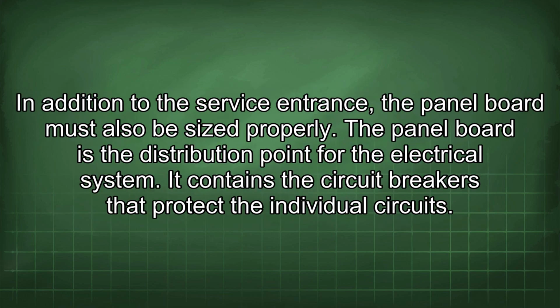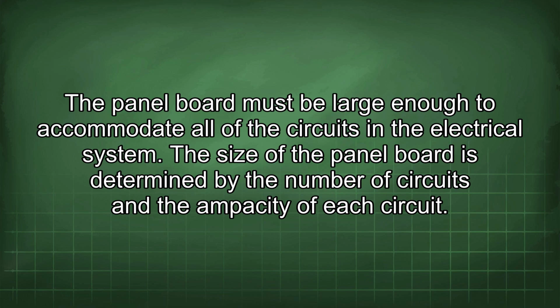In addition to the service entrance, the panel board must also be sized properly. The panel board is the distribution point for the electrical system. It contains the circuit breakers that protect the individual circuits. The panel board must be large enough to accommodate all of the circuits in the electrical system. The size of the panel board is determined by the number of circuits and the ampacity of each circuit.